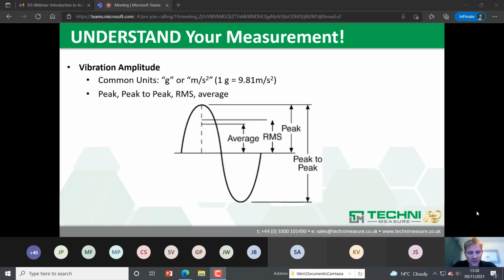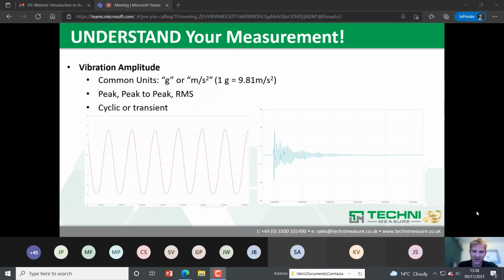Something to be quite aware of is that people will use different notations, and it's very important to know that you're speaking the same language if you're talking to somebody else about specifying an accelerometer. The peak G or range of an accelerometer or of a specimen movement or vibration measurement task, versus the peak to peak, versus the RMS, versus the average, all mean different things. If you're not careful, you could both be talking about different metrics, and therefore you could be up to a factor of 2 out. So just make sure you're on the same page if you're discussing vibration measurement with anyone and when you're looking to choose an accelerometer. Also, as Keith mentioned, are you looking at a cyclic measurement, or are you looking at some kind of transient measurement, as some kind of structural response to an impact or some event? That can drive the way you go about choosing your accelerometer as well.